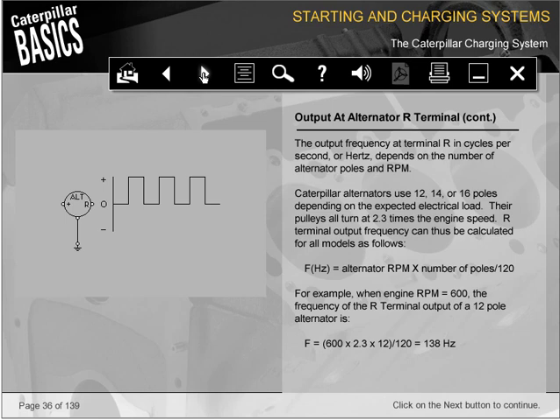Frequency, Hertz, equals alternator RPM multiplied by the number of poles divided by 120. For example, when engine RPM equals 600, the frequency of the R terminal output of a 12-pole alternator is: frequency equals 600 times 2.3 times 12 divided by 120 equals 138 Hertz.